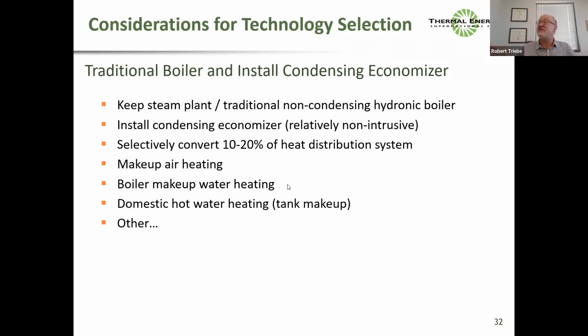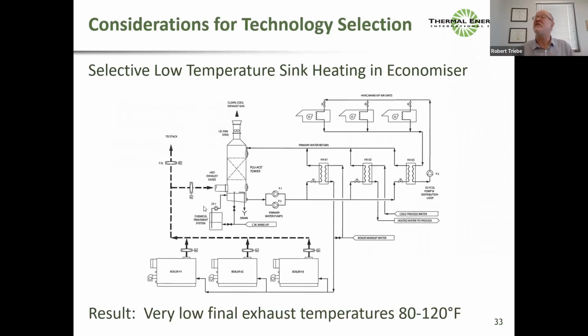So other considerations: installing condensing, selectively convert, yes, makeup air heating. That's one of the good ones, by the way. Hospitals typically have a bunch of 100% fresh makeup air. You could do that with a really cold circuit. You could put a separate glycol circuit. You could go out at 120, and in the wintertime, you can come back at 60 Fahrenheit. You could do all the air heating, but you don't have to convert the whole plant. Just convert a couple big air makeup units to take advantage of the low temperature of that heat sink, and then hook up that low temperature heat sink to the economizer, not to the entire circuit. Boiler makeup heating, domestic hot water heating can all be done with heat recovery.